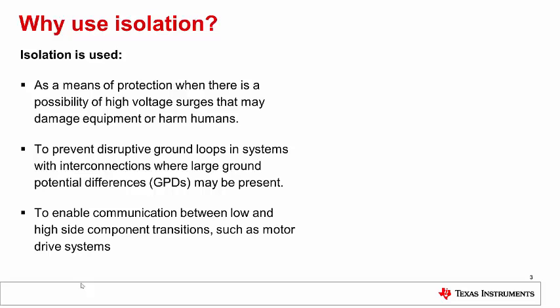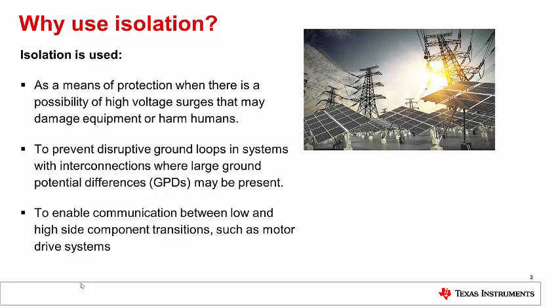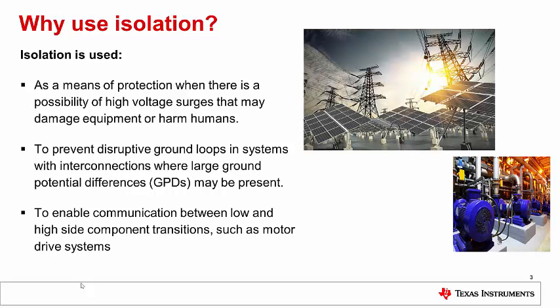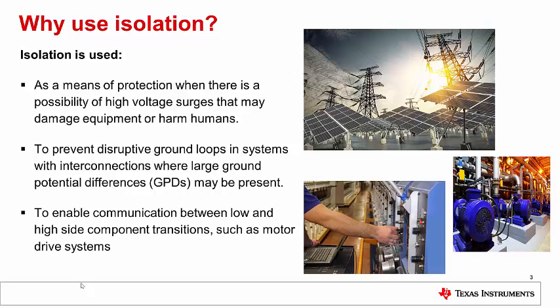Why use isolation? Isolation is used as a means of protection when there is the possibility of high voltage surges that may damage equipment or harm humans. It also prevents disruptive ground loops in systems with interconnections where large ground potential differences, or GPDs, may be present, and to enable communication between low and high side component transitions, such as in motor drive systems.